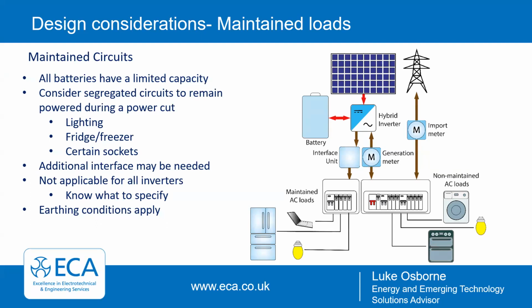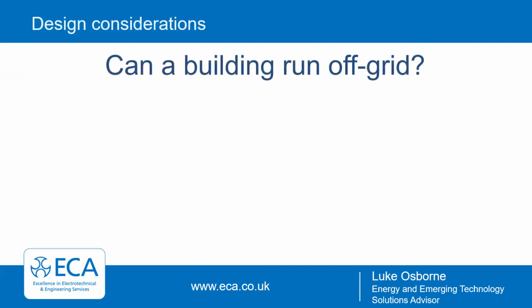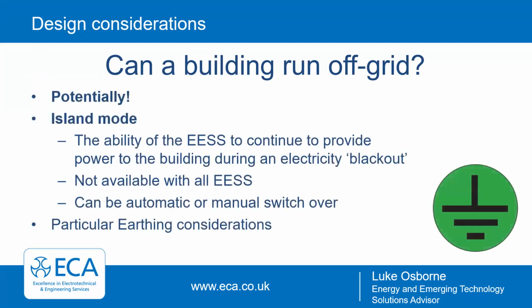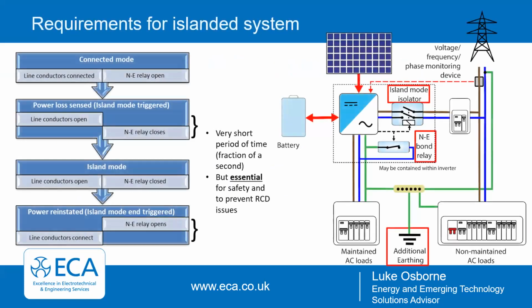But there are specific earthing conditions that apply in these scenarios. So with this, people ask, can they run a building off grid using these technologies? Well, they can - this is island mode, and this is what needs to be specified. It's the ability for the battery storage system to continue providing power during a blackout. It's not available on all battery storage systems, and these can operate either automatically or by manual switchover, but there are particular things that need to be considered.